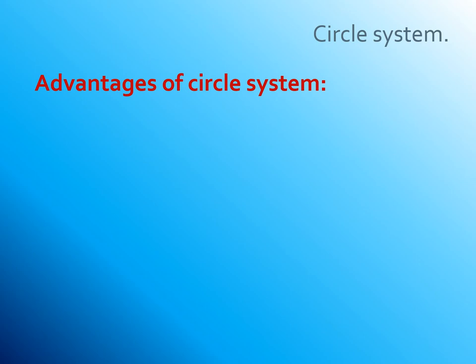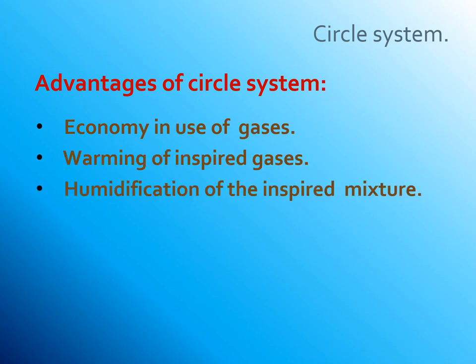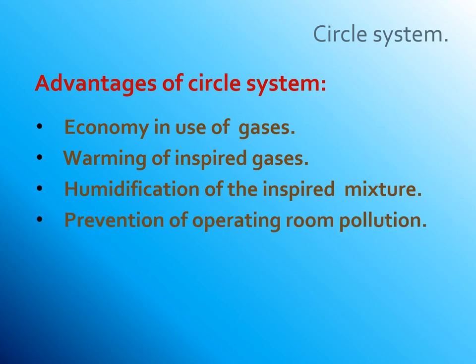Advantages of the circle system: it is economical because very little gas is used compared to other circuits. It provides warming of inspired gas and humidification of inspired gas, because the patient re-breathes warm, humidified expired gases. It also prevents operating room pollution because it is a closed system.